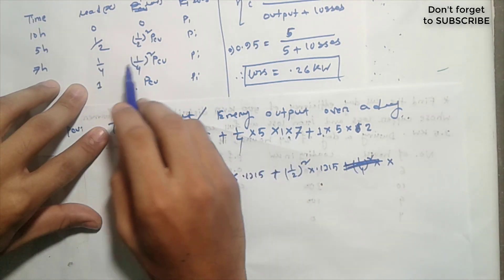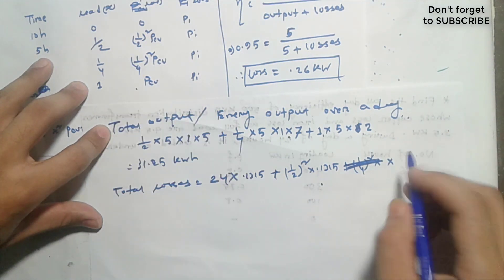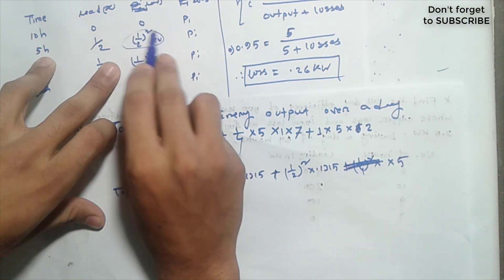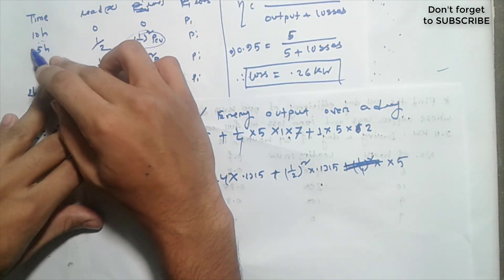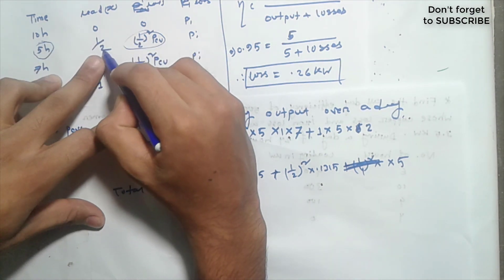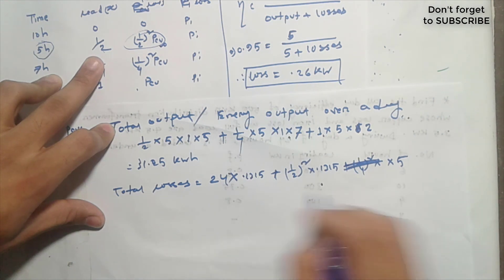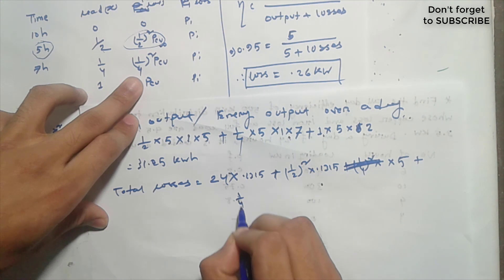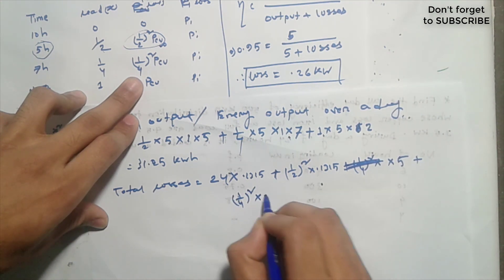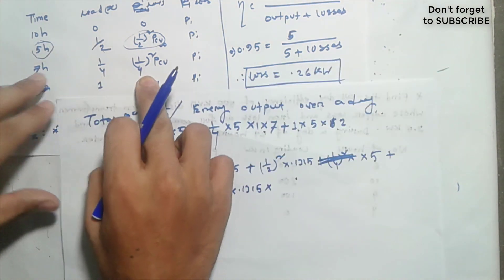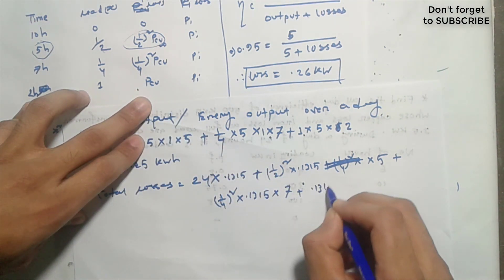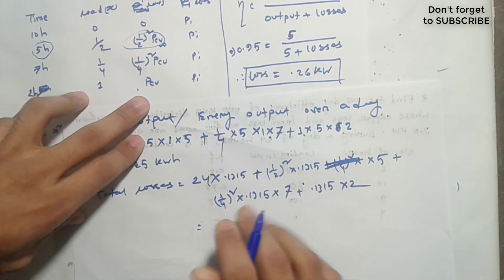We have 5 hours at half load, so the copper loss for that period is half-squared into Pcu. For the quarter-load period: 1/4 squared into Pcu, which is 0.1215 kilowatts multiplied by 7 hours. For full load: 0.1215 into 2 hours. We sum all these to get the total copper loss over the day.